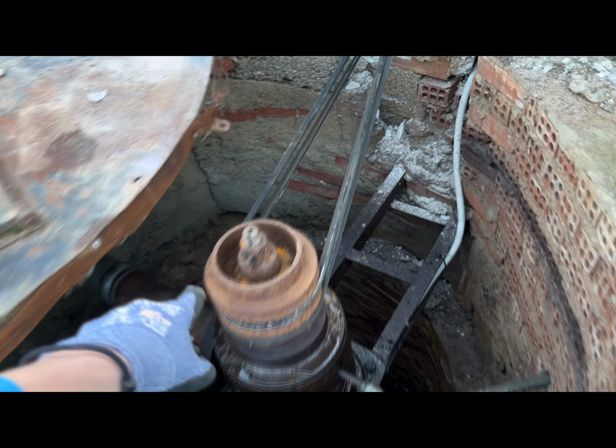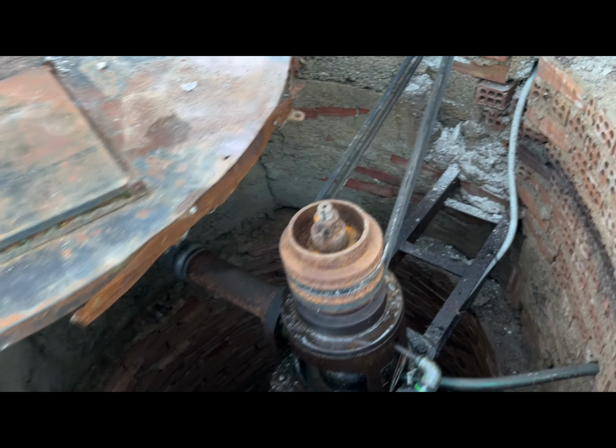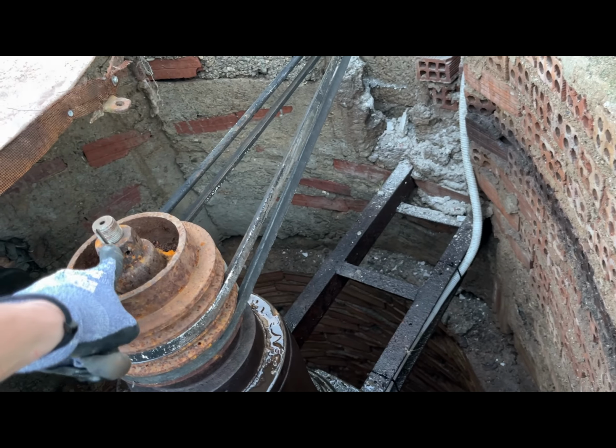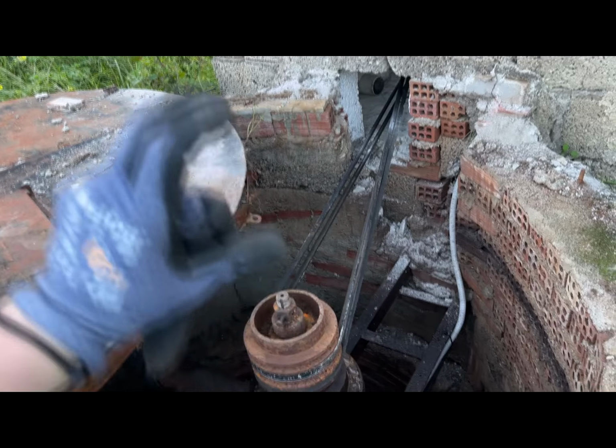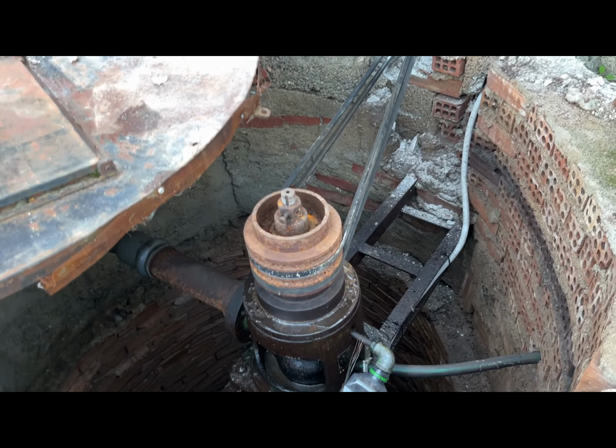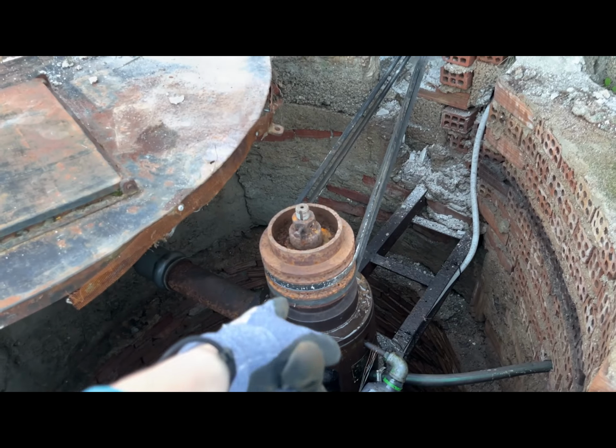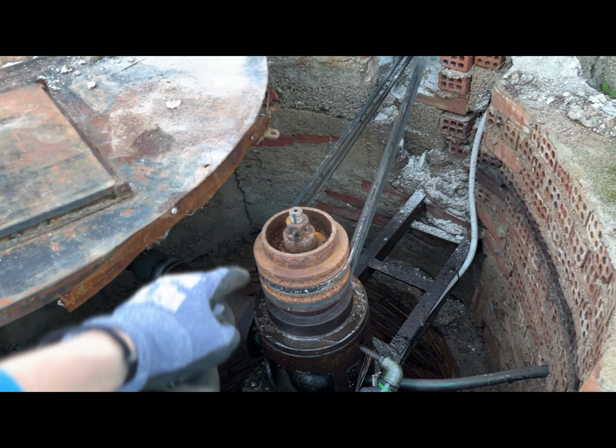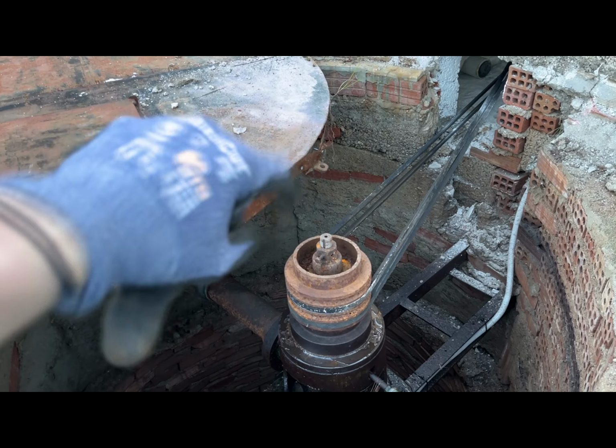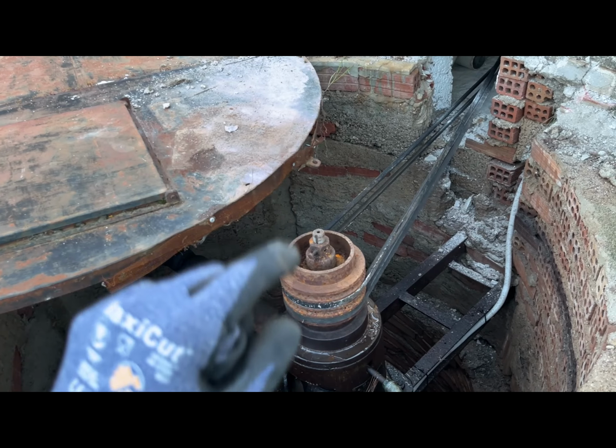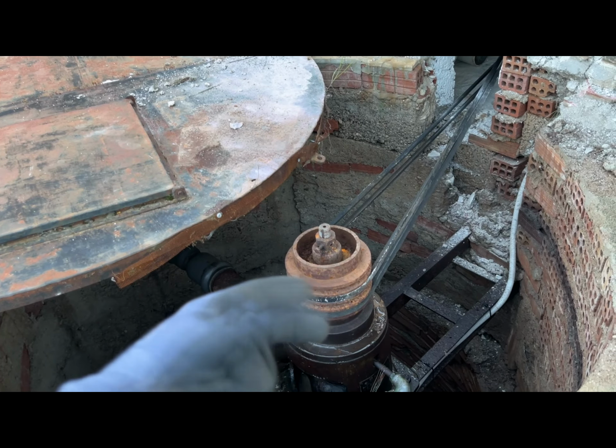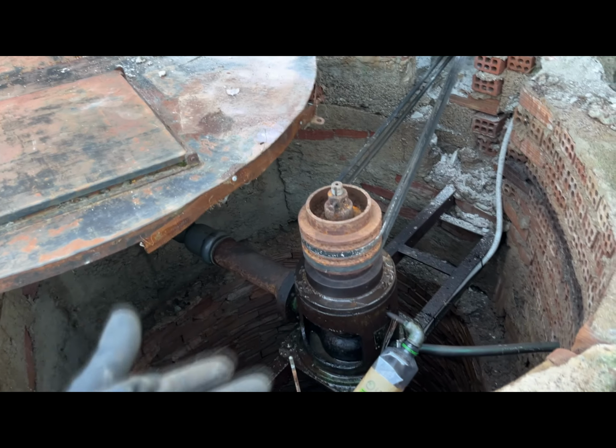But before you loosen this nut, you want to measure its depth, because it adjusts how the impellers sit down there. Ideally, get the information from the pump manufacturer, which tells you how many turns to turn it in order to adjust it properly, after it stops touching the bottom, the impeller stops touching the bottom.